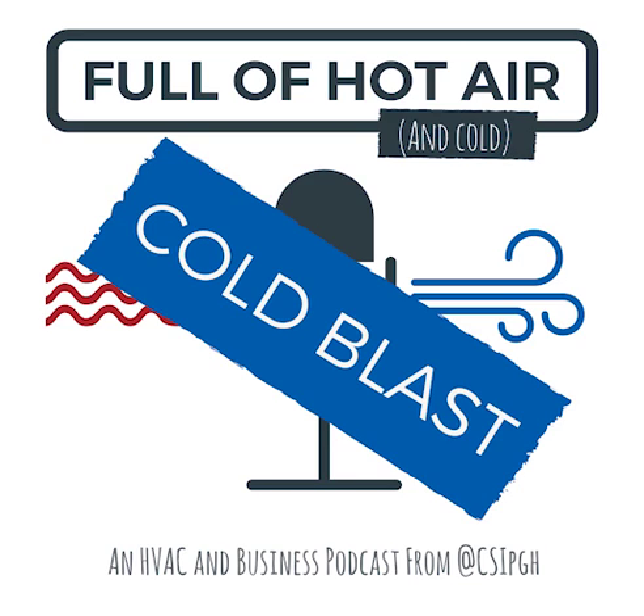To know what that duct system is doing for you is very important as well. So how do I know my airflow on an existing system without actually running all the sizes, all the runs? It's a lot of work. There's an easy way to figure out what the airflow is in a system. Whether it's an air handler or a gas furnace, we can do it with either, as long as the air handler has electric heat installed in it, which most of them do. It'll usually be a heat pump system.